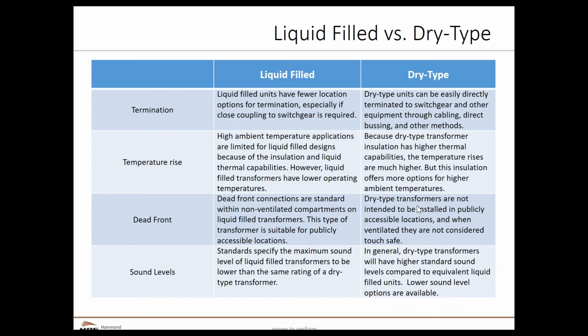And you have to be careful when you say dead front construction. Typically, the way we would interpret that with a dry type is we bring all the connection points into a separate terminal, often called an air terminal chamber. And then we have a dead front construction on that specific air terminal chamber. However, there are additional access points to the main transformer, and those are typically open because we would have some difficulty in blocking those off with some type of dead front construction for the cooling characteristics. Again, you can do it, but it's not really the way most people would.